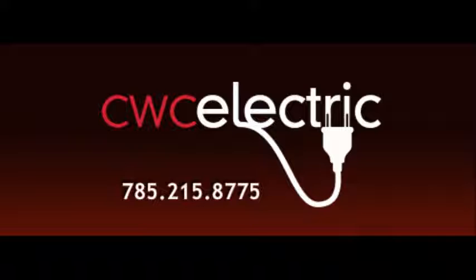And so a circuit breaker by design is supposed to be the weakest link in your electrical system. It protects everything else. So it is the weakest thing. The wire, the outlet devices are all stronger than it. If you overload it and it doesn't trip when it's supposed to, then you're operating the wire, the outlets, the devices at a much higher amperage than they're designed for. Well, amperage equals heat, and you start doing serious damage to the house. So I cannot emphasize enough that the Federal Pacific Stab-Lok panels have to be replaced.